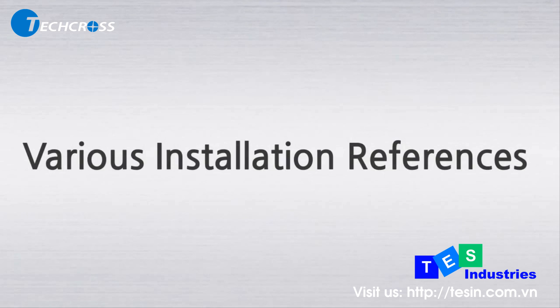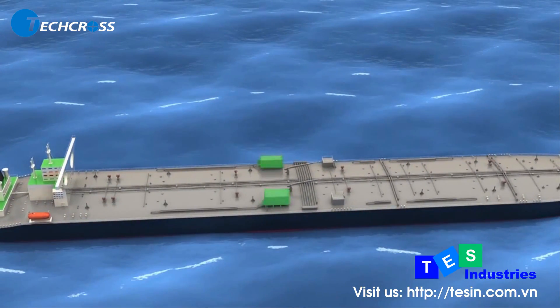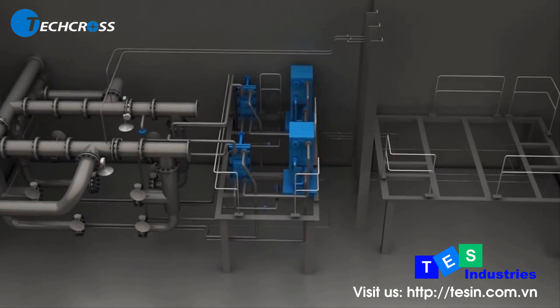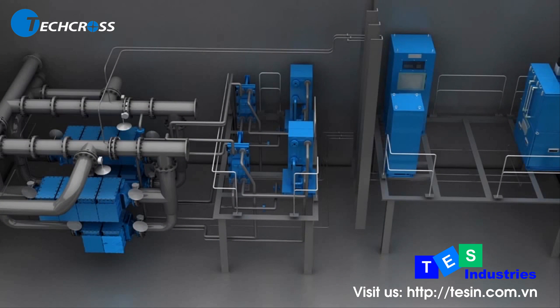TECHCROSS provides various installation solutions for each project to meet the needs of shipyards and ship owners. For tankers with no pump room but a submerged ballast pump, a safety room can be made on deck. Explosion-proof type ECU and other equipment are installed in this room with a skid mount. Non-explosive equipment is installed in the engine room for aft-peak tanks.